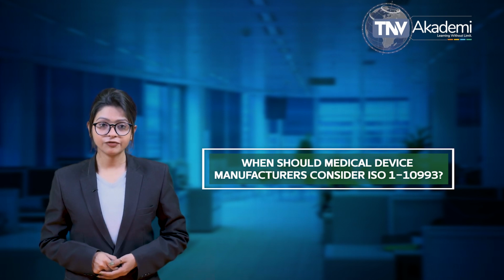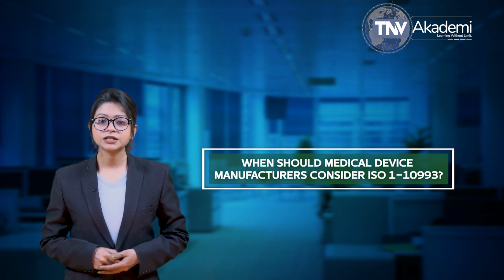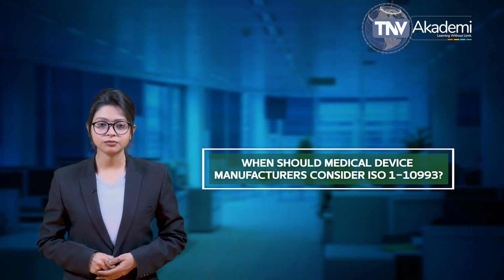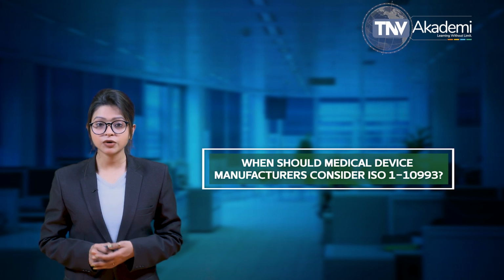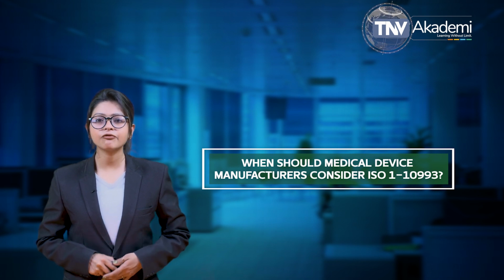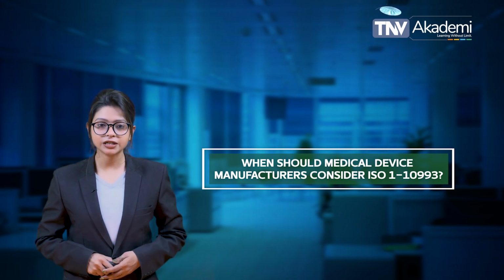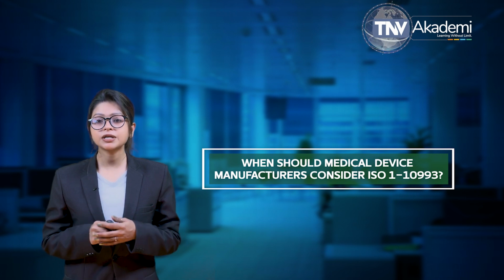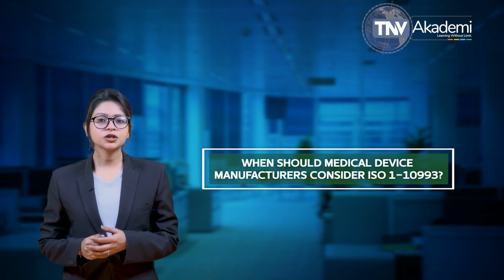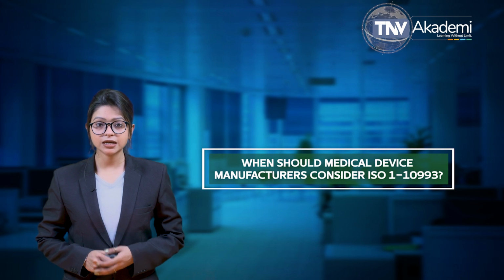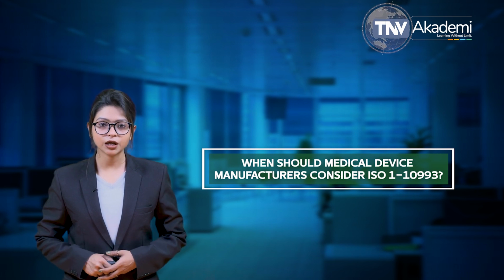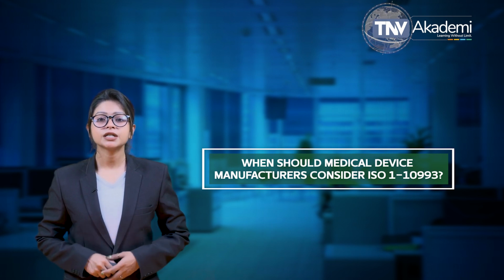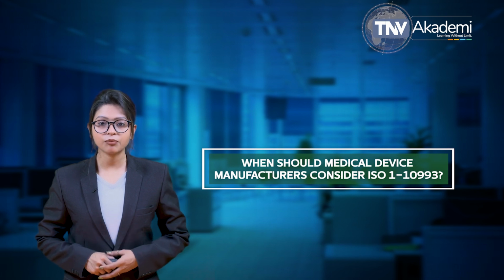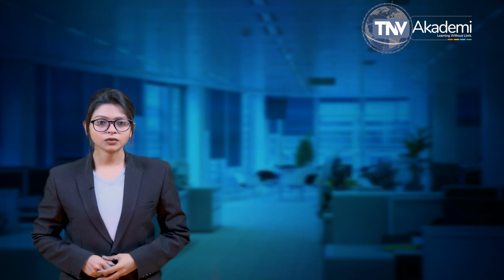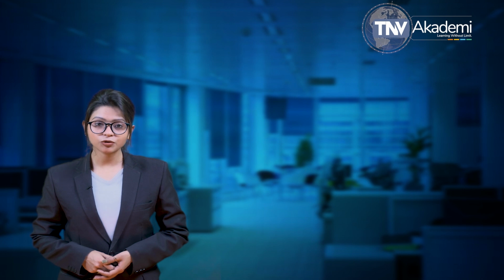This will also help fill in some of the gaps in the timeline for regulatory submission. ISO 10993-1 should also be considered when there is a change in the medical device's manufacturing process, material or supplier. These changes can have unintended consequences for safety and may require testing to demonstrate equivalence to the initially approved or cleared product. So let's move forward to our last point of discussion.